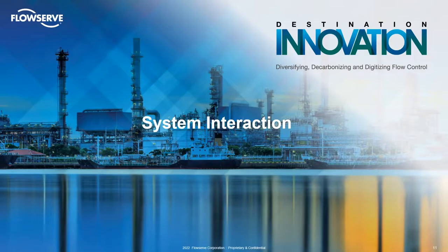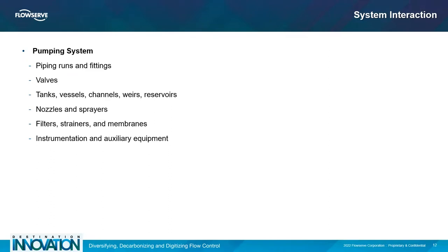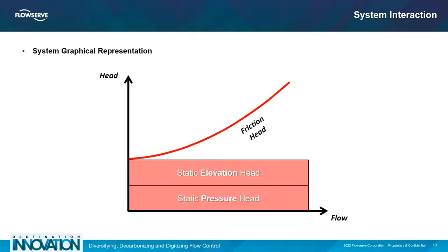A deeper dive into the system will help to understand how excessive throttling restricts pump system longevity. The pump system is anything that ties the suction source being drawn from to the delivery source being discharged into. This includes piping runs of specific hydraulic diameter, valves, strainers, and fittings. Each component within the pump system will carry a certain amount of differential pressure, elevation, and friction to be overcome in order to induce flow.